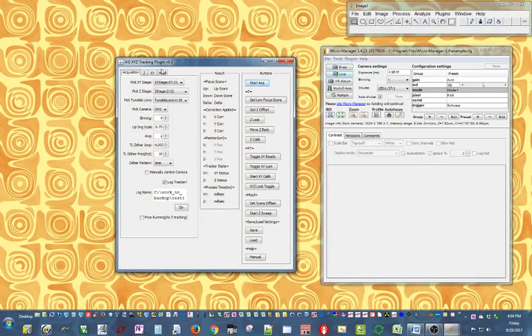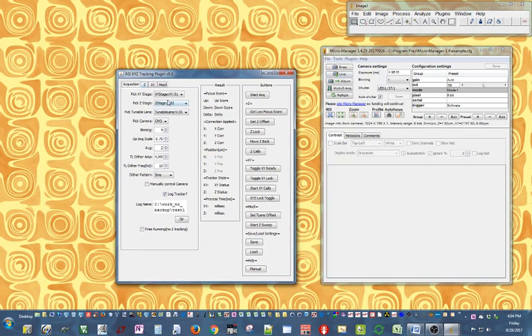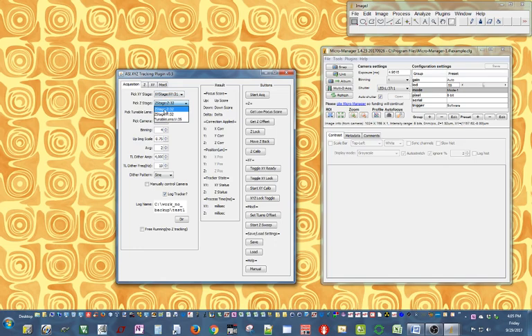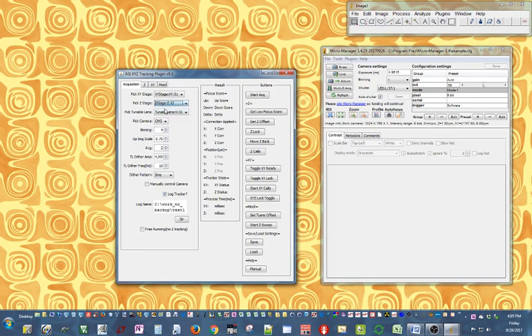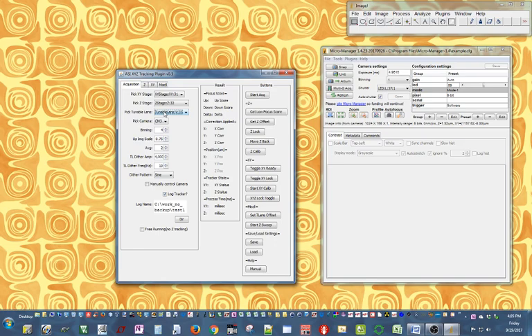Let's launch the plugin. The plugin's acquisition window lets you pick the devices the plugin can use. For XY stage, there's only just one. For the Z, pick the one that's correct - this is the one that has the objective attached, and this will move the objective. Or you might have your focus drive attached to the stage instead, so the sample is moved. Whichever it is, pick that. The tunable lens - this is the tunable lens that's controlled by the tunable lens card. By varying the current, the tunable lens card is able to change the focal length of this lens. This lens is sitting in an assembly right in front of the camera, and by changing the focal length of this lens, we're able to change the focus of the image the camera is getting without actually moving the objective. The Z tracking application relies on this. The camera we want to use.